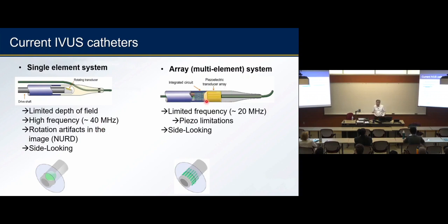And array technology is actually what got me into this business, because even in the 1990s, they were able to put 64 element arrays, think about my fingers wrapped around, and then they put 4 or 5 silicon chips to connect to each one of them. So you can imagine there are around 250 electrical connections made in that small volume. The nice thing is you don't need to rotate it mechanically. With a phased array, you can rotate your beam electronically. So this became a big seller because it's easy to use. But the problem with that technology is that it's usually limited to lower frequencies, because making those smaller piezoelectrics wasn't very feasible, and it's still not very feasible.